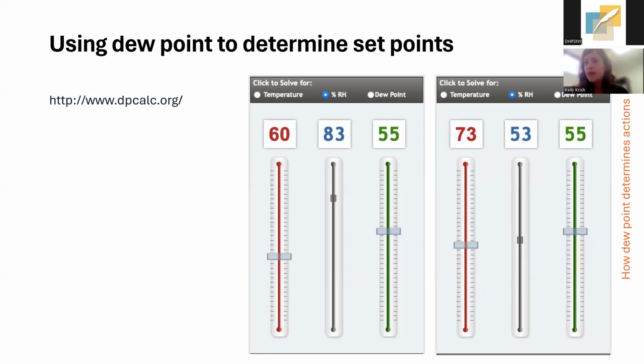I hope that's useful. So we talked about how dew point can be used to see when there are times of the year that there's loads coming from outside, and how we can evaluate the effectiveness of different mitigation measures. This would be another way, how to determine set points. So again, I would lock in that dew point, and then I would lower the temperature until the RH hit the point where I no longer felt comfortable with it going higher. And that would be how I could establish my upper limit for summer.